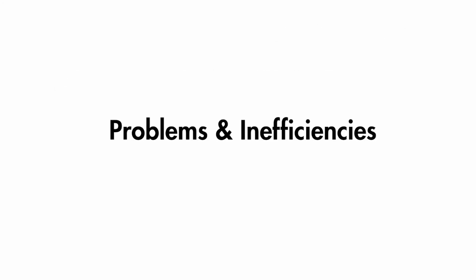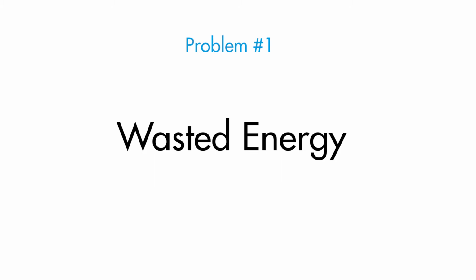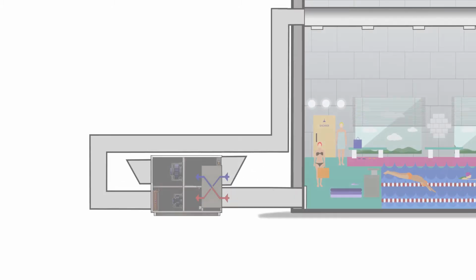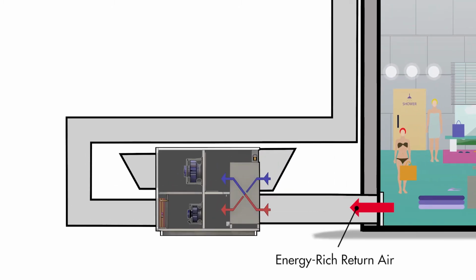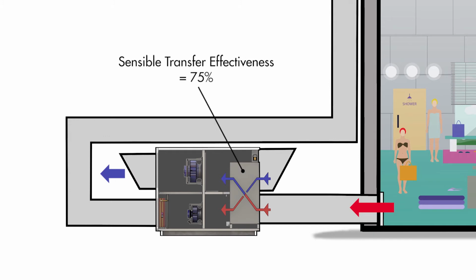So now let's go over the problems or inefficiencies of a typical pool facility like this. Problem 1. Wasted energy. Large amounts of energy goes to waste when the energy-rich humid indoor air is exhausted outside, even when a heat recovery ventilator is used. Let's say, for example, the sensible heat transfer effectiveness of a heat recovery ventilator used in a pool application is 75%. This means that 75% of the temperature difference between the outside air and the return air is transferred between the airflow paths and energy is reclaimed.